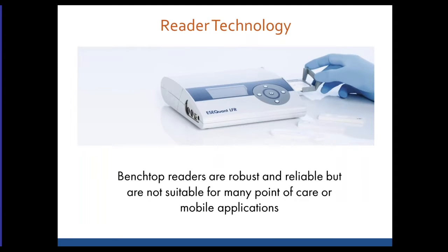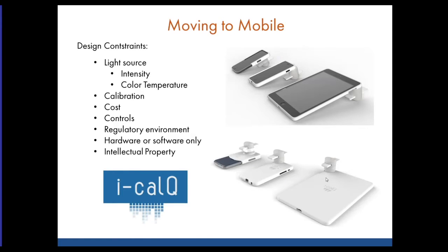The other exciting development in lateral flow is readers — the ability to quantify results. With your eye you're good at yes/no, but for actual numbers you need a machine readout. Benchtop instruments exist but are not suitable for point-of-care or mobile applications. One company we've been working with is iCalQ, which has developed hardware that attaches to cell phones and iPads, bridging the gap between visual reading and quantitative measurement. Design constraints for such readers include light source, color temperature, calibration, cost, controls, regulatory environment, and intellectual property.